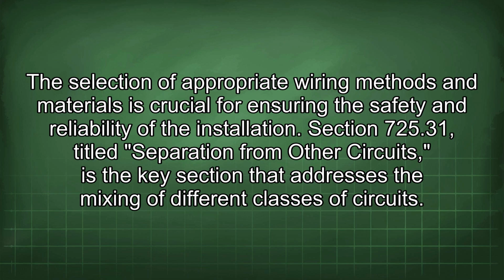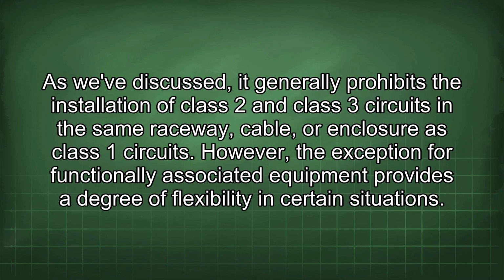Section 725.31, titled Separation from Other Circuits, is the key section that addresses the mixing of different classes of circuits. As we've discussed, it generally prohibits the installation of Class 2 and Class 3 circuits in the same raceway, cable, or enclosure as Class 1 circuits. However, the exception for functionally associated equipment provides a degree of flexibility in certain situations.